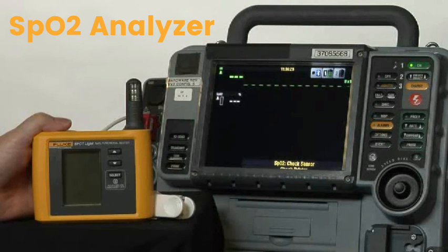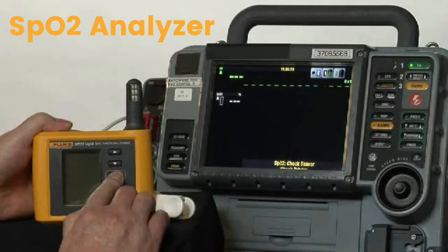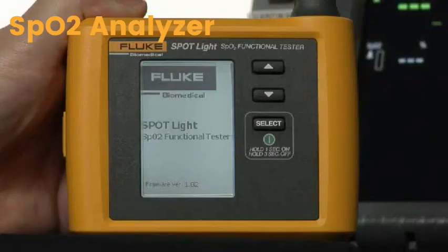Grab your spotlight and go up to the clinical unit. In this case, we find the device turned on. It's a defibrillator. And we will turn on our spotlight SpO2 functional tester. Wait for it to go through its self-check.